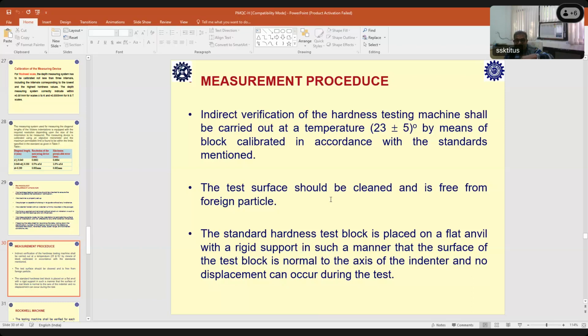Whenever you make any indentation on the sample, because of the force, sometimes the sample will curve. It can bend, because it is a very natural thing, if the thickness is not sufficiently maintained. Normally the hardness blocks come with 6 mm thickness, sometimes 15 mm thickness. 6 mm is sometimes good enough, but when you are using a 6 mm hardness block and apply force, it can sometimes curve, by applying a large number of forces. Because of that, your supporting surface will not be proper. The supporting surface gets damaged because of the continuous indentation and because of the thickness of the sample. But in some cases, even the supporting surface can develop some flaws or rust, or some foreign particles may be sticking to the bottom surface.